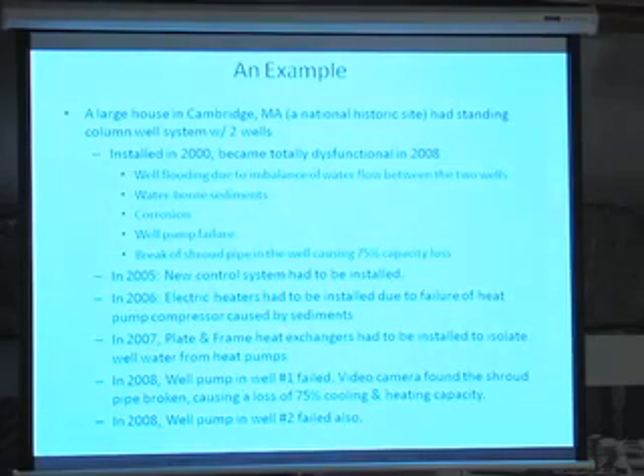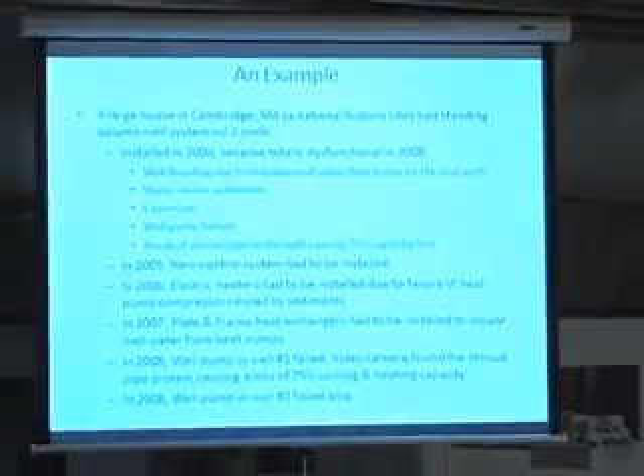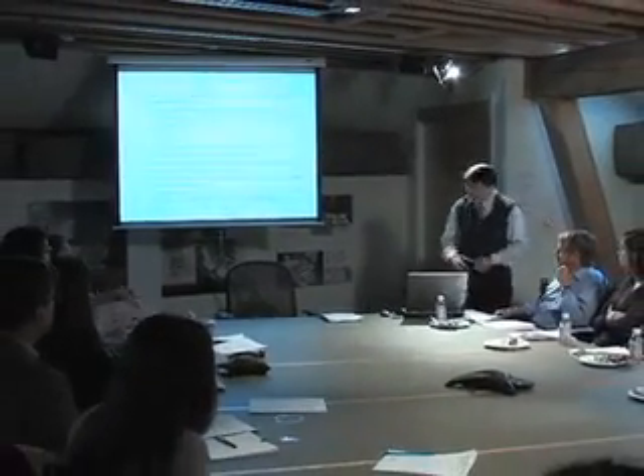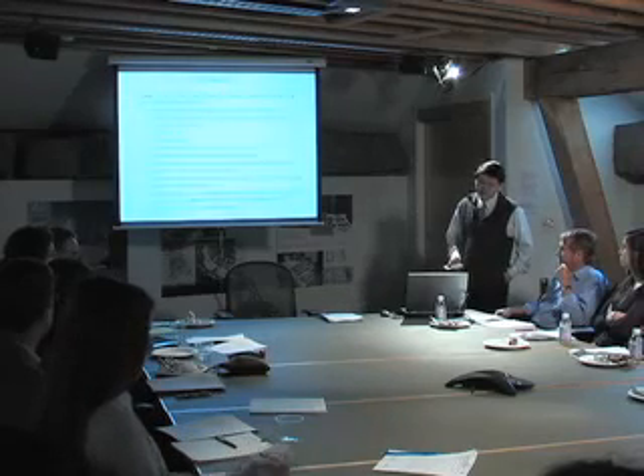In 2006, they had to install electric heaters because the compressors failed. In 2007, they had to put in heat exchangers to isolate the well water and the inside loops, the heat pumps. In 2008, the well pump failed, and they used a video camera and found out the shroud pipe was broken, causing a loss of 75% capacity. The same year, the other pump failed as well. Do you have any idea why all that happened? Corrosion, yeah. Sediments, bad design. I don't think they had an engineer on it. I think the equipment vendor did the whole thing.